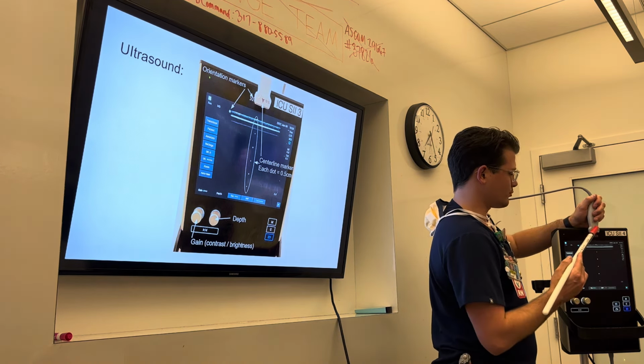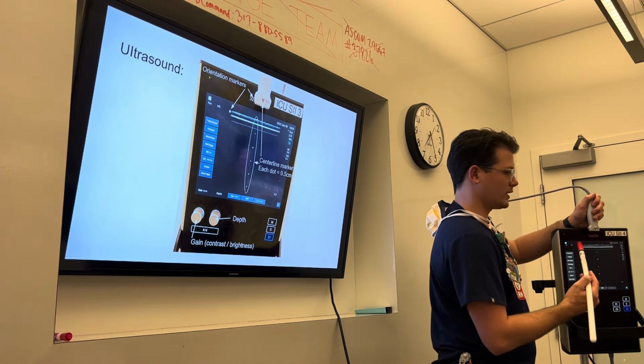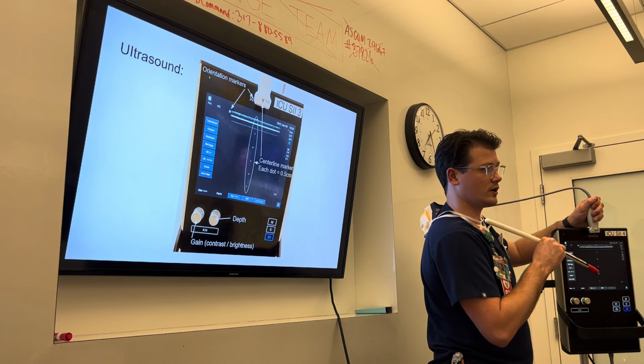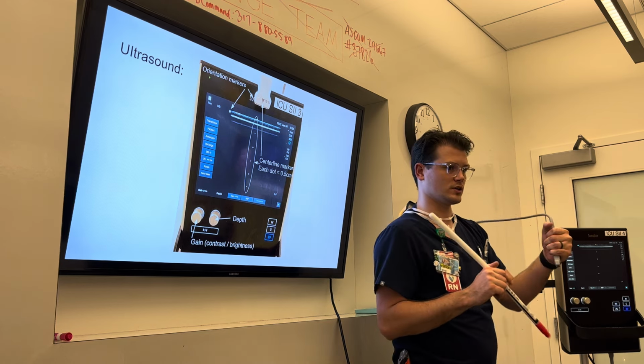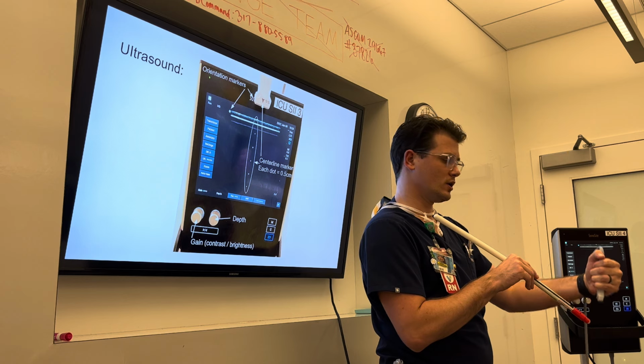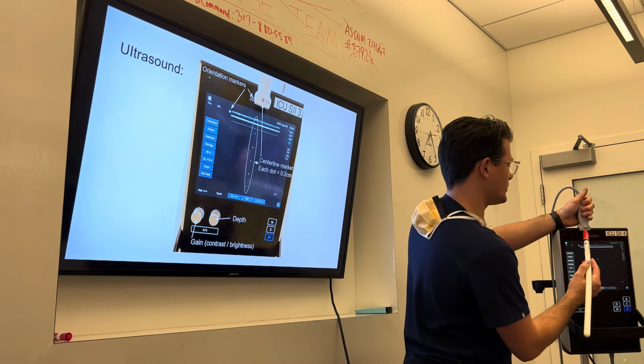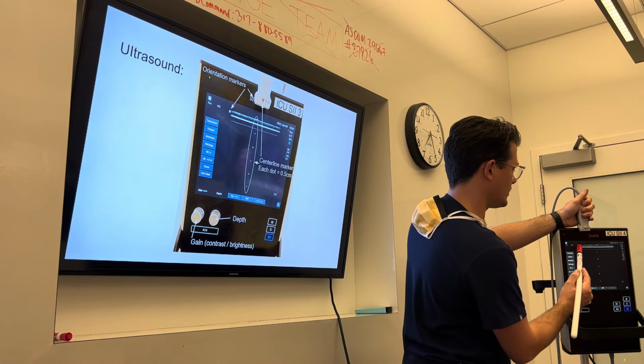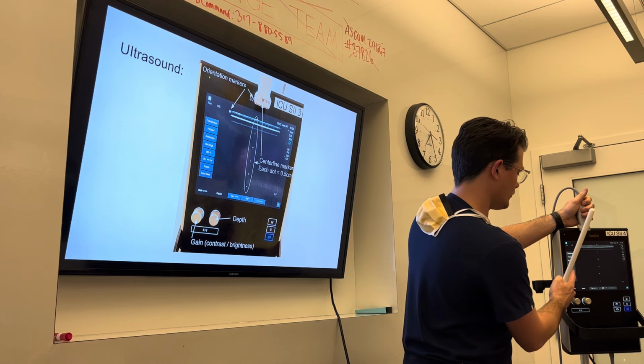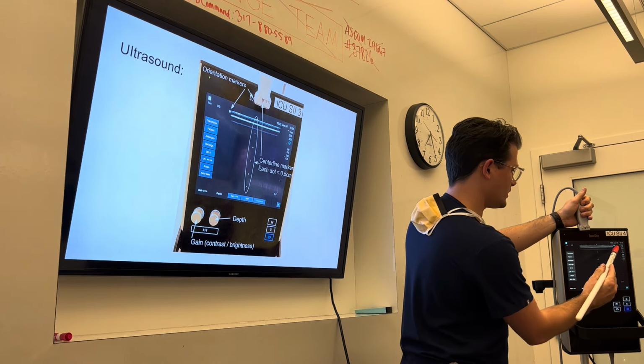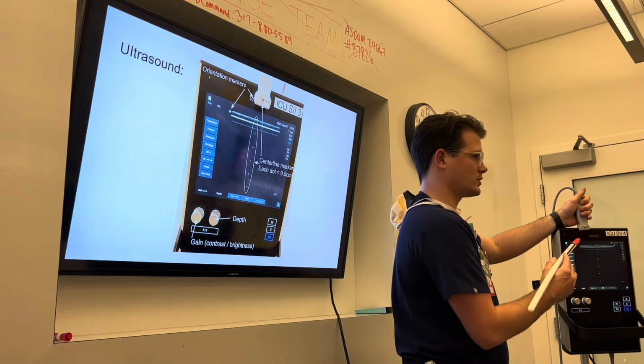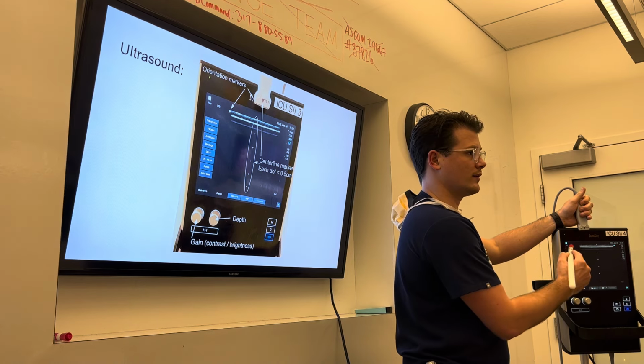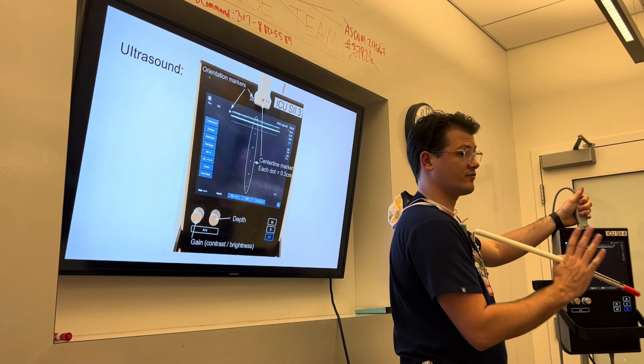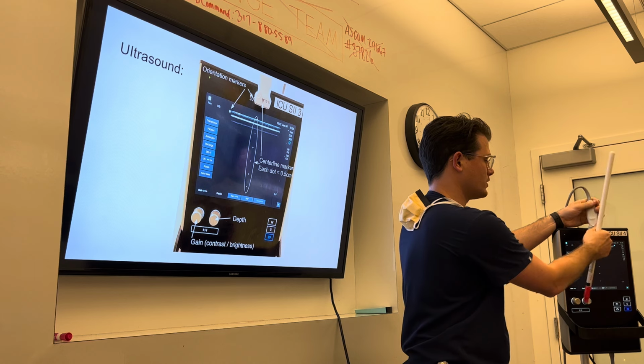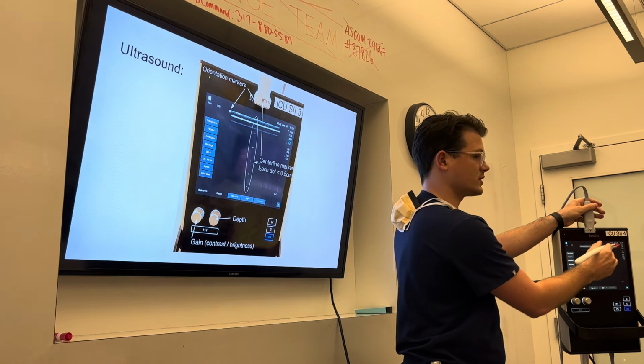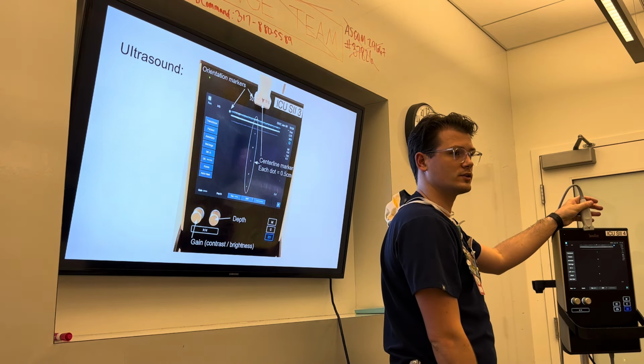The reason that's important is because when we're looking at our image, we want the left on our screen to be left based on where we're at on the patient. The way you know that's lined up is the orientation marker is on the left and this little blue dot's on the left. If we switch the blue dot to the other side, we're actually seeing an inverted image, so the left is on the right and the right is on the left. To fix that, all you have to do is make sure your orientation marker is on the same side as that little dot on the screen.